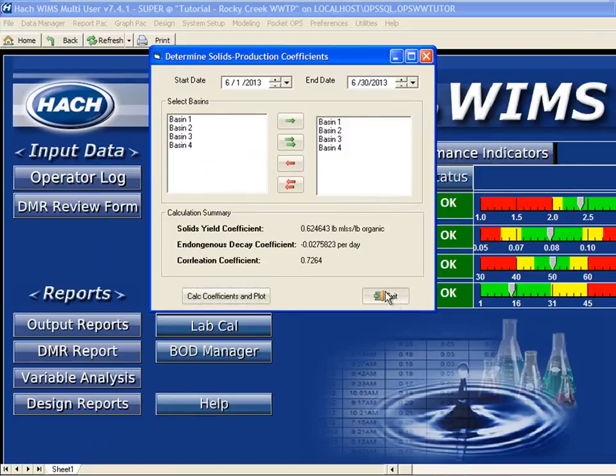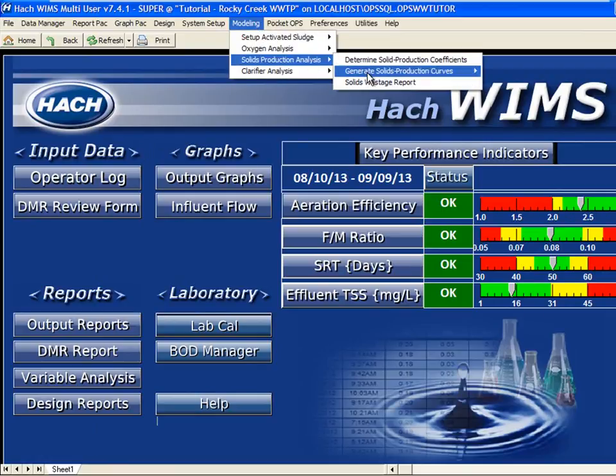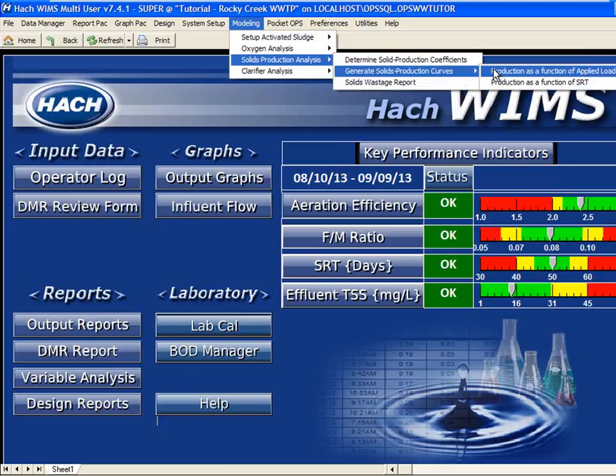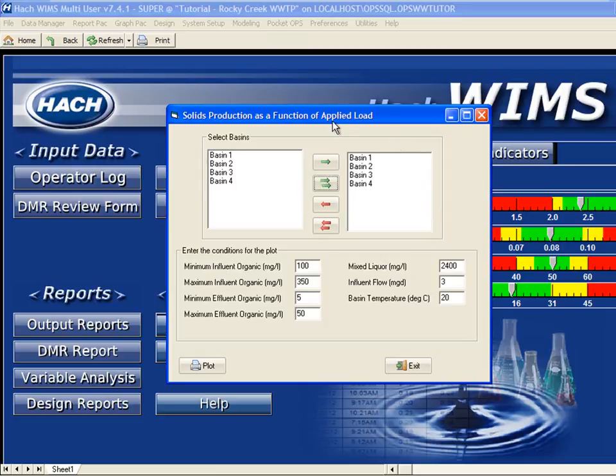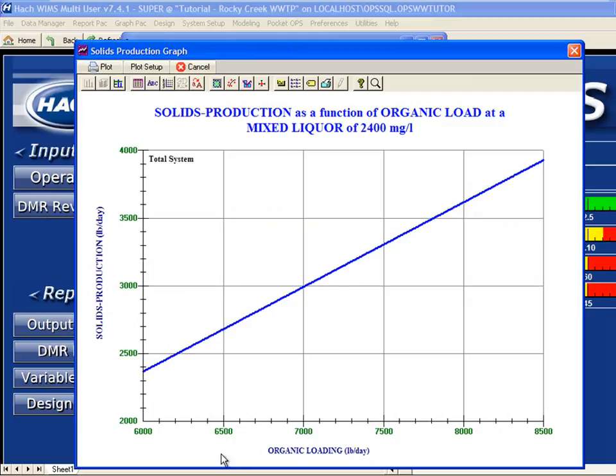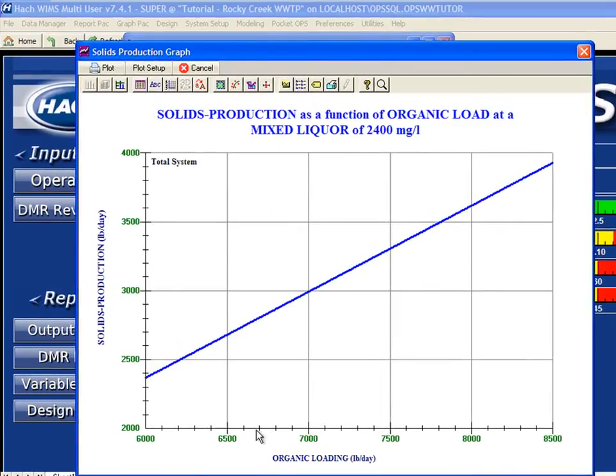Once I've produced my coefficients, I'm now ready to analyze my data. I go into Modeling and generate some solids production curves. First, I want to look at production as a function of applied load, running all four basins. I set my operating conditions: Influent Organic BOD somewhere between 100 and 350, effluent from 5 to 50, and I want to operate my mixed liquor at 2,400. I can then plot and see, at a mixed liquor of 2,400 and given certain organic loads, how much solids I'm going to produce.